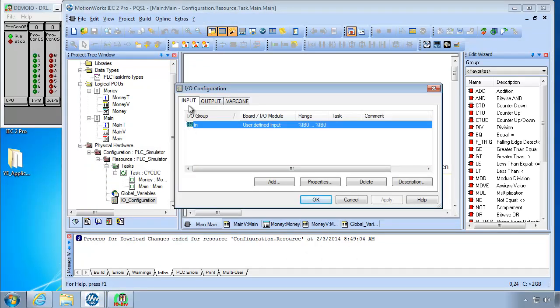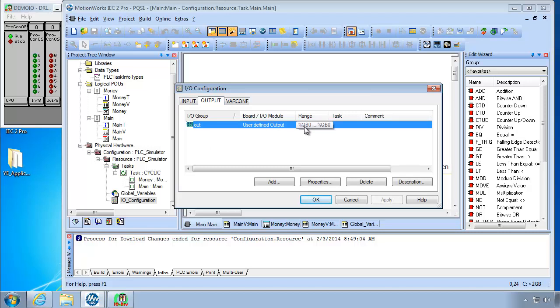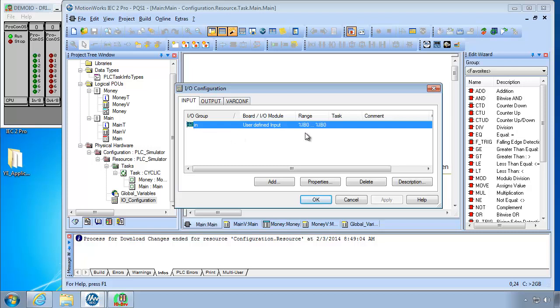Just double click to open that and you'll see that there are inputs and outputs and a range. IO configuration is in the project tree at the bottom. And you can see this here there's a tab for inputs user defined input. It says %IB0 not an X but you get the idea %IB0 means a byte 0. And then the output also %QB0 they use Q for outputs so as not to confuse with the letter O or the number 0. So this IO configuration is what determines where a particular input or output module is used in the memory location of that particular PLC.